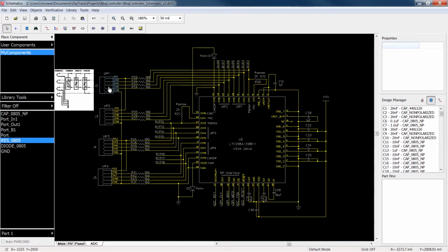I've got 1, 2, 3, 4 universal inputs on our new temperature controller. Tell me that's not sweet. So now if you want to put a thermocouple for the chamber probe, or 2-wire, 3-wire, 4-wire, thermistor, anything you want to use, you can just swap it out. It should work, that's the theory anyway. This hasn't been tested, so don't hold me to this. But the chip does have to be reconfigured.